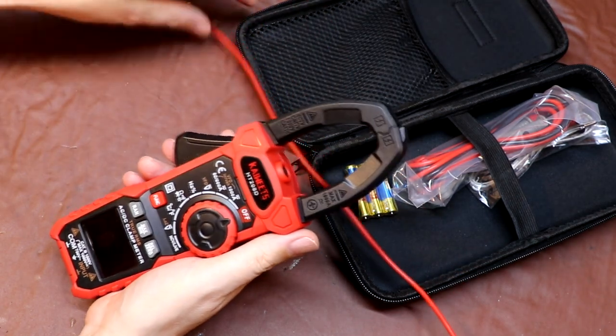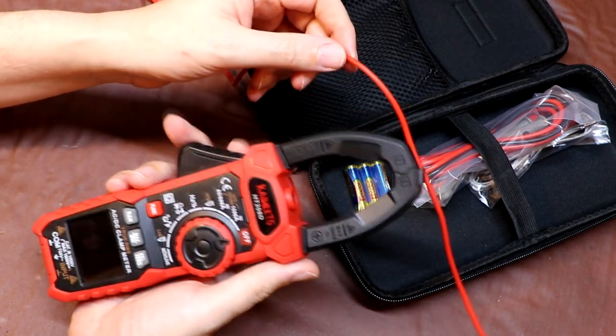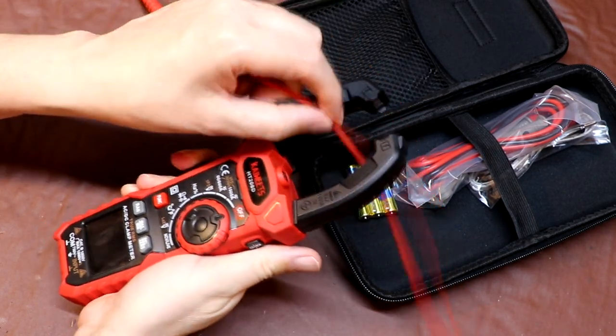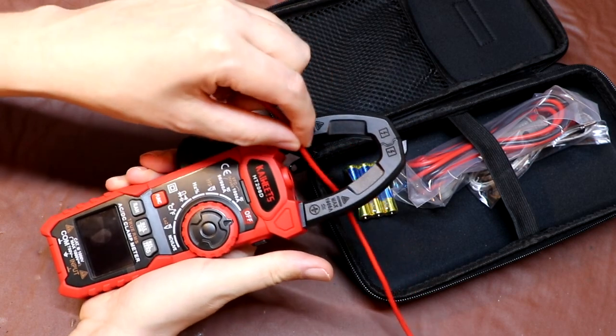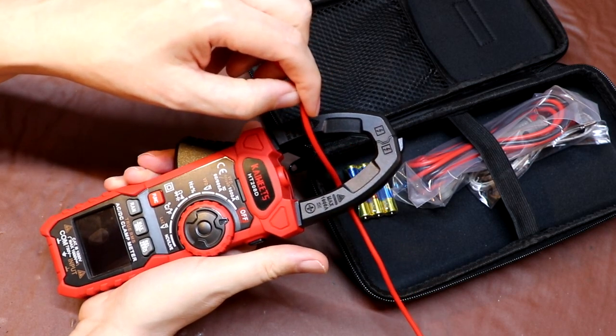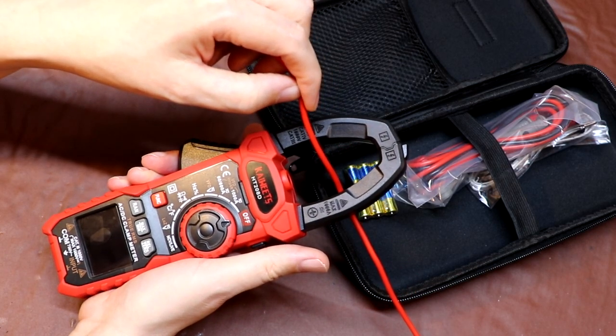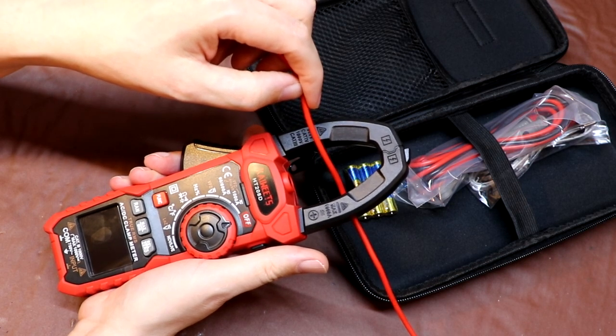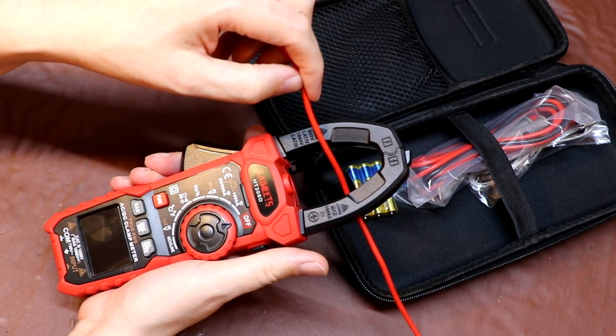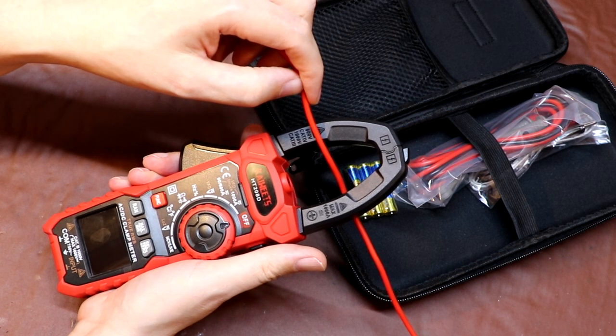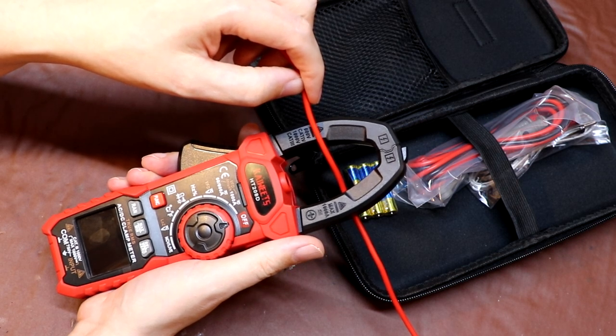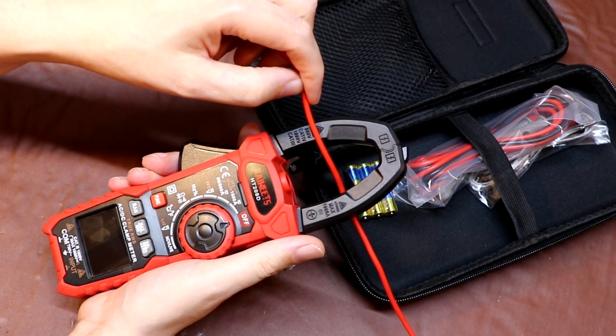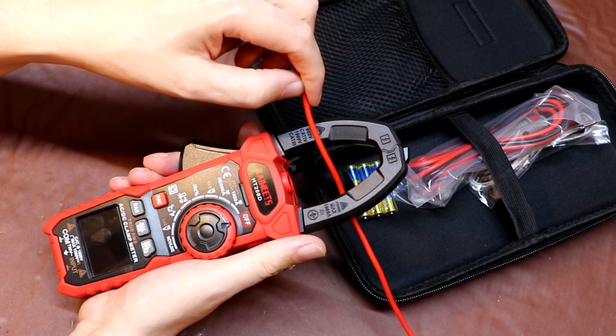If we've got a wire that we want to measure the current going through, all you actually have to do is open up this clamp assembly, clip the wire in, and then it can make a current measurement. Now there's a few advantages of that. Sometimes it isn't practical to actually disconnect the circuit so you can install your current meter because you might not be in a position to switch the supply off. Certainly if you were supplying something like a house or a machine, you wouldn't necessarily want to switch that off just to do a current measurement.